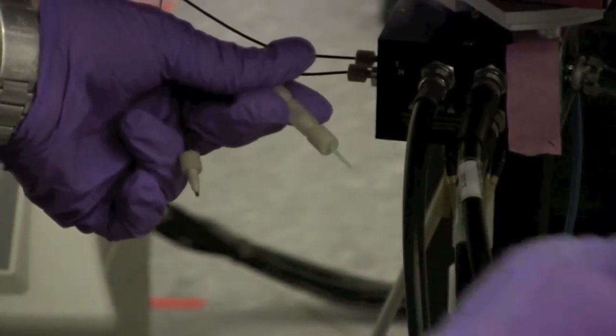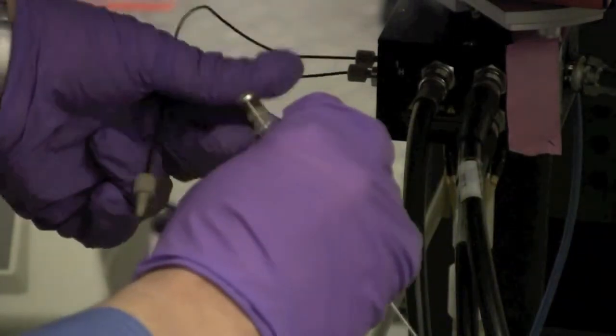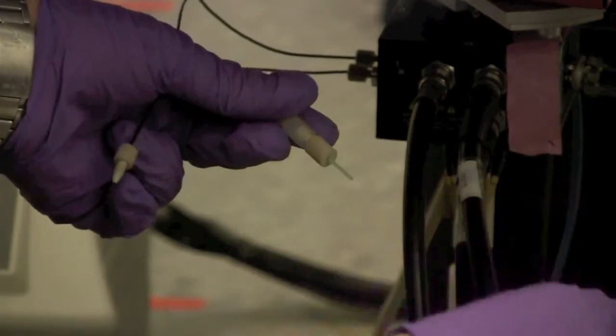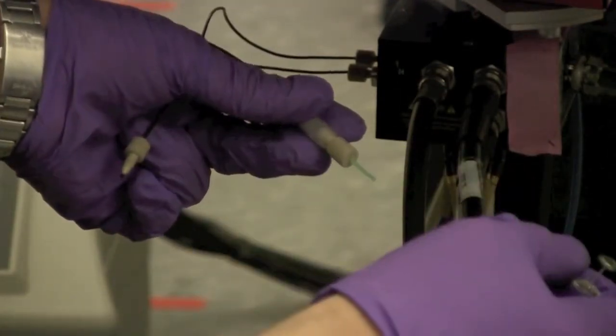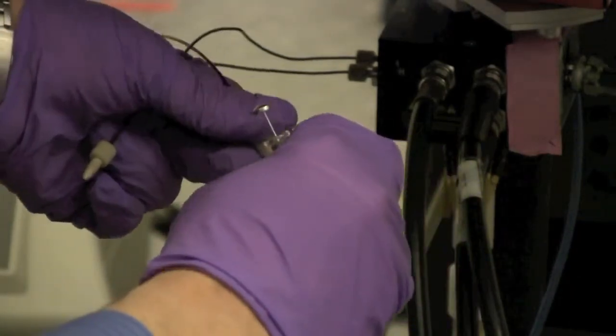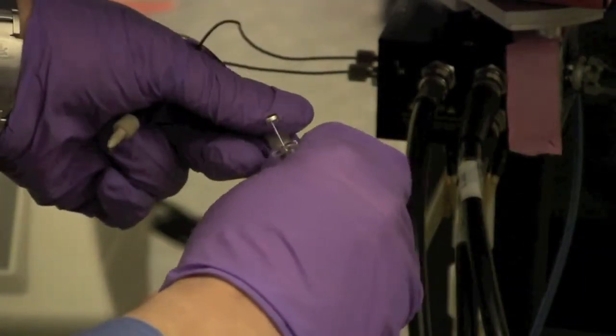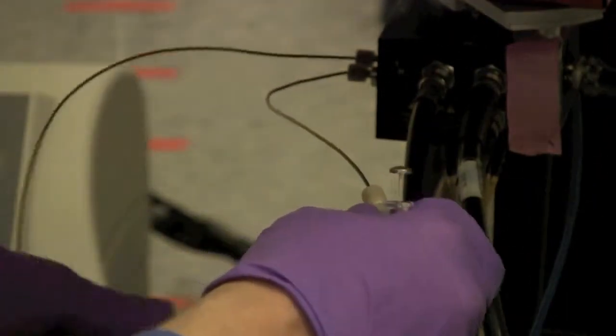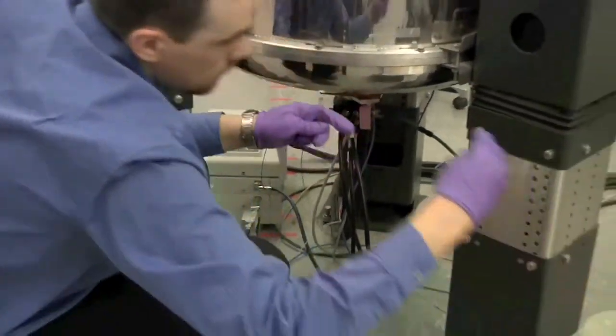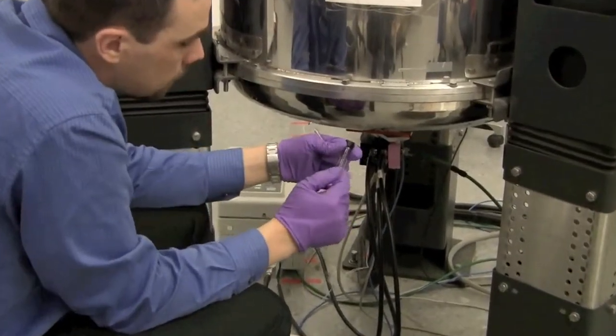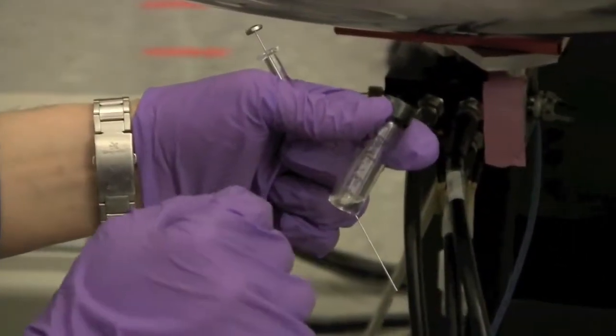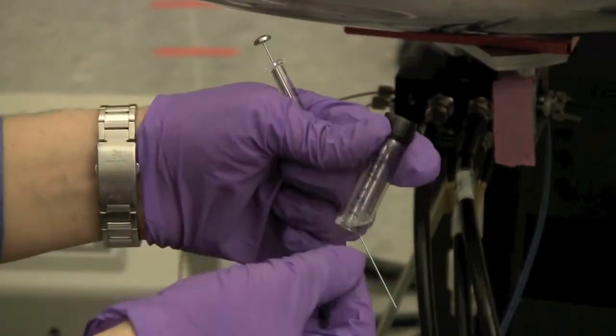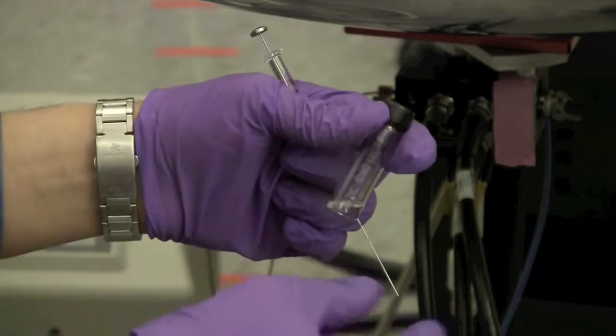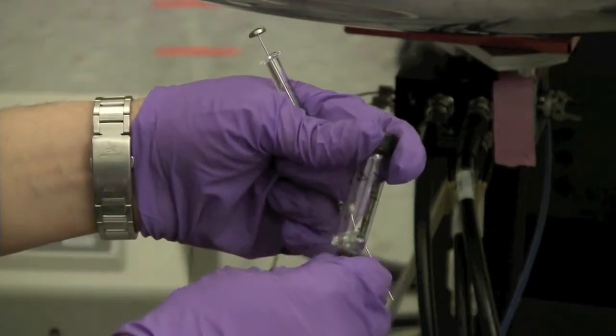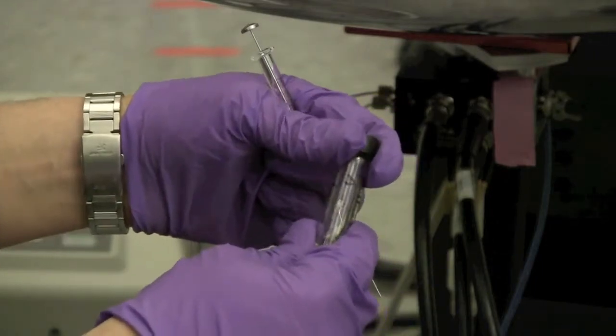The tip of the syringe and the inlet are probably the most likely causes of contamination from carryover from one person to the other. So you want to make sure all these pieces are clean before you load your sample into the probe. In this case, I'm fairly confident that they're clean, so I'm going to go ahead and load our sample. I have a sample here in a vial. Remember that when you're preparing a sample that it needs to be filtered just like it would for the automation system. You can use the centrifuge filtration method if you prefer. If you have filtered it for HPLC, that's probably sufficient.